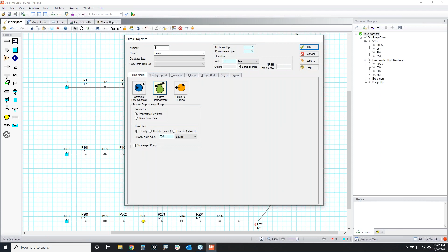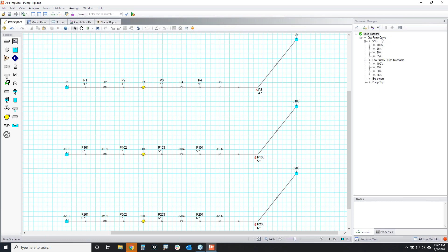All right. So in this particular scenario, again, this model comes from Fathom. It was something that I imported into Impulse. So in my steady state simulation, what I did was I started off by sizing my pumps, my pipeline, and my tanks. And so this is how I did that, where I had a certain design flow rate through my pump that I wanted to meet, and I didn't know the pipe size, so I guessed 4-inch, 5-inch, and 6 inches in diameter. And I went through that whole madness to size my pump.